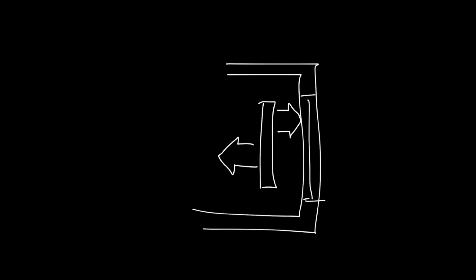Now let's take a look at the 50-50 compromise from a plan view perspective. We'll place a 4-foot diffuser about 18 inches from the window typically. It will have two sets of 2-foot pattern controllers. One set will be set to blow towards the window, and the other towards the interior of the space. Again, this is our 50-50 compromise. And although it does work well to address both applications, we're only getting half of the air in the needed direction at any given mode.